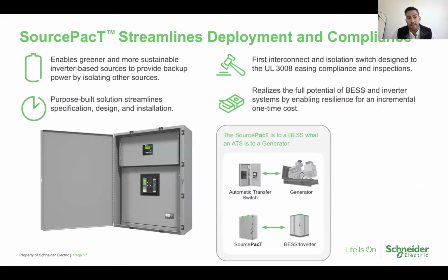And we like to use the analogy: what an automatic transfer switch is to a generator, SourcePacT is to a battery energy storage system. And what we mean by that, and we'll go through a couple of examples here, is today in the industry, there's not really a purpose-built product that's designed specifically to isolate from the primary service, have the controls within that device to communicate to the energy storage system that you're safely isolated and to enable battery resilience. And of course, why do you want to enable battery resilience is during your grid connected operation, which probably 99% of the time you're grid connected. You get the availability to call on a cleaner, more sustainable energy storage system to provide backup power.